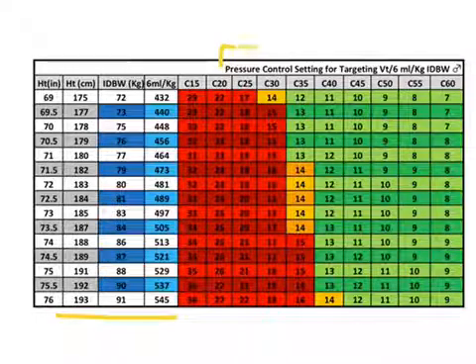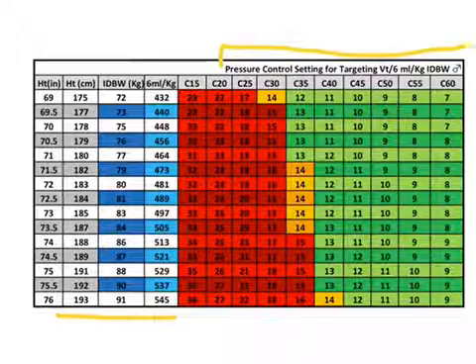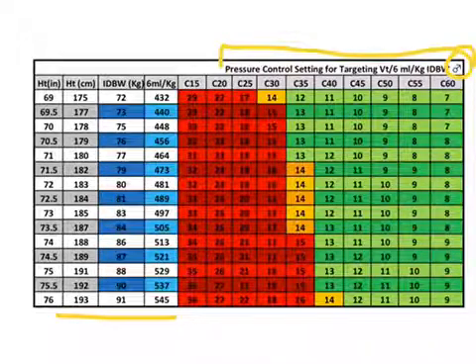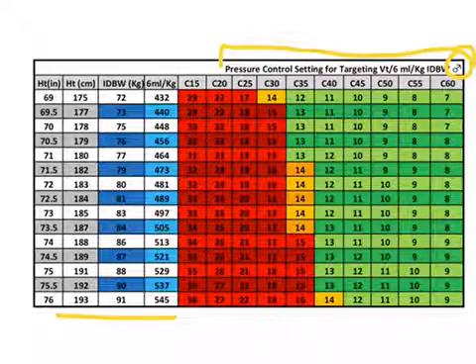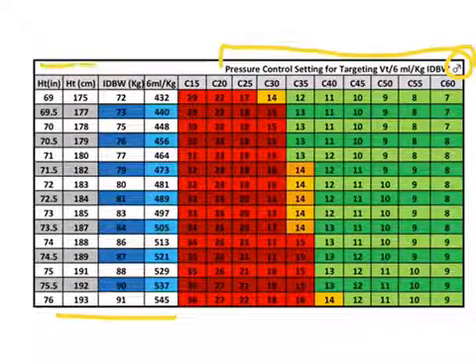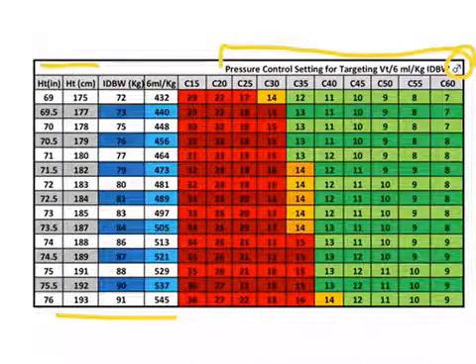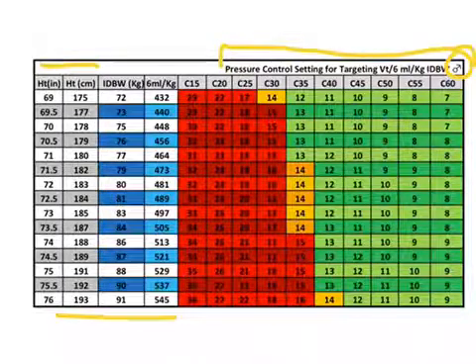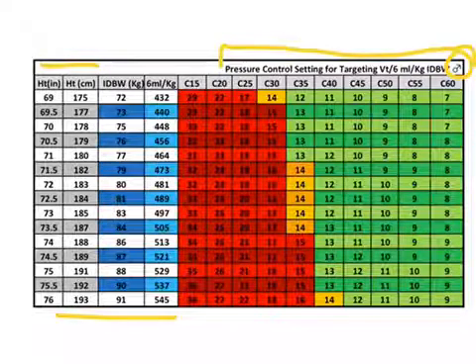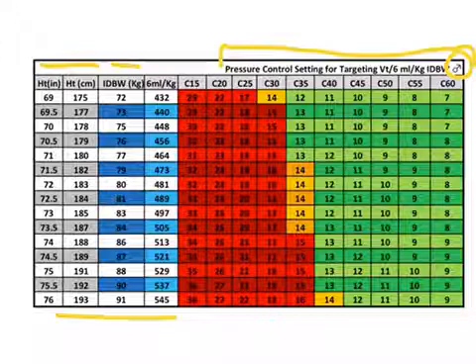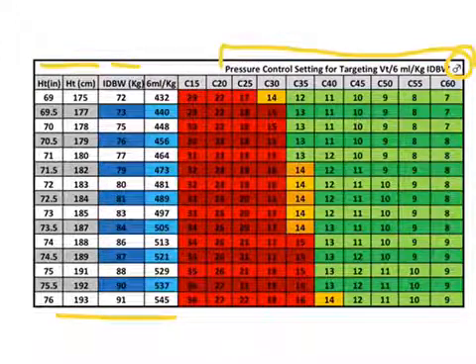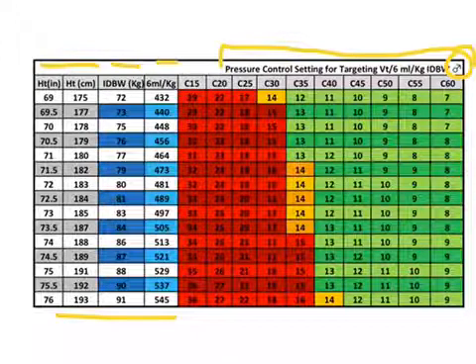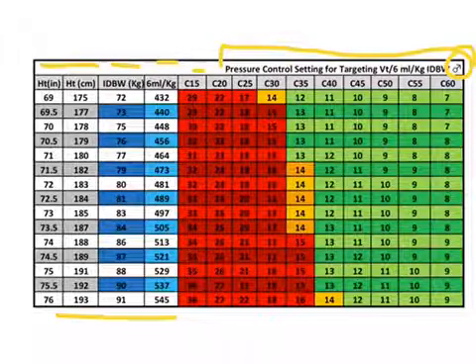The other inputs are my height, so I need to know the height of the patient in either inches or centimeters and that gives me multiple outputs. It gives me an output for my ideal body weight, my tidal volume if I was targeting six cc's per kilogram and my compliance variables too.